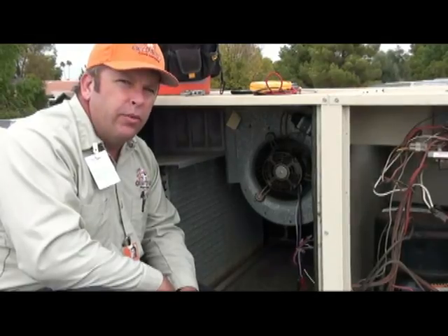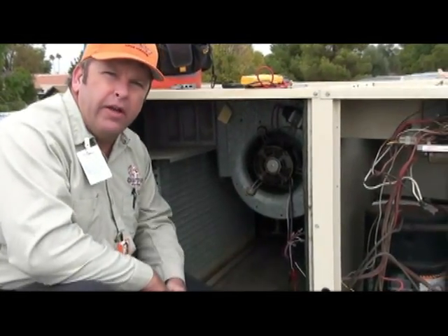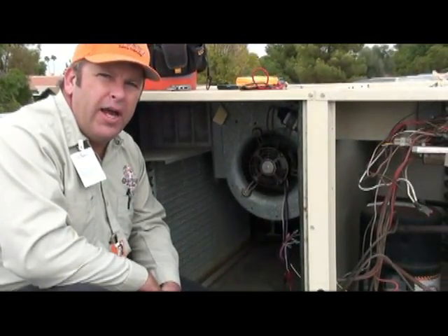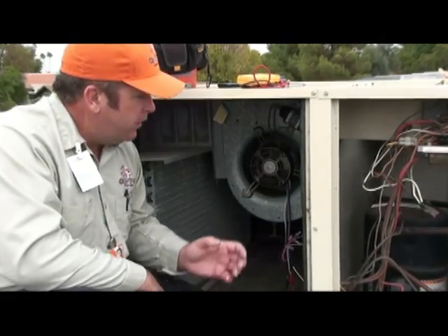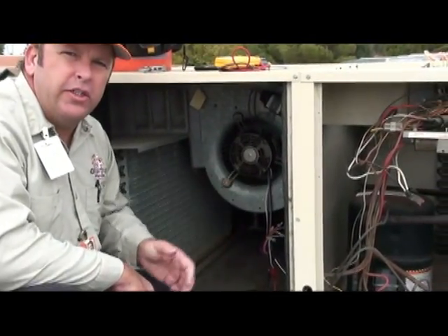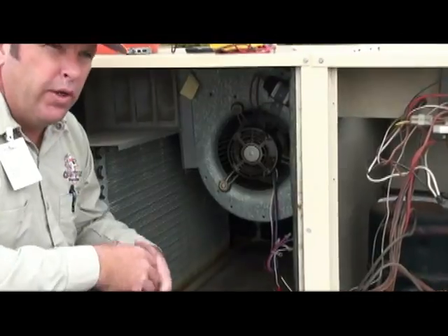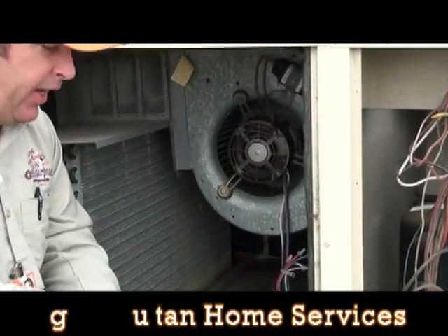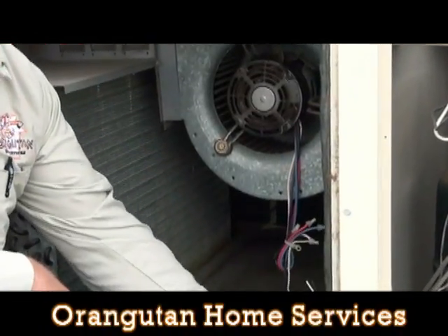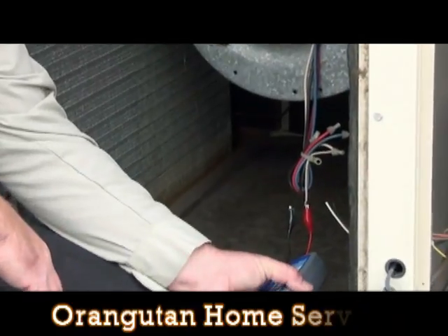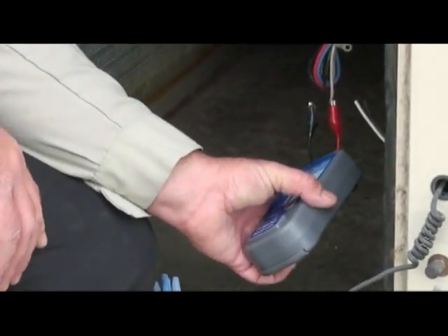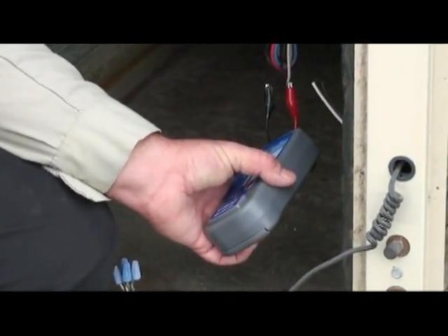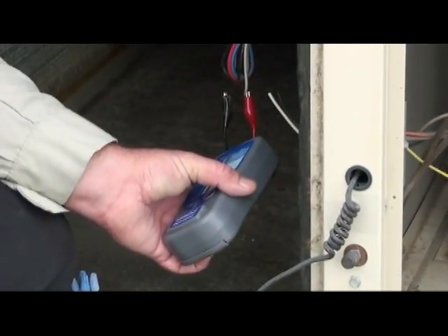The second failure mode on the blower motor is called low resistance. The windings within the blower motor are insulated from heat. Over time and running conditions, those windings and the insulation start to break down, which creates even more heat. We use what is called a mega ohm meter to check those windings and the actual decay of the winding and how bad the corrosion or decay has become.